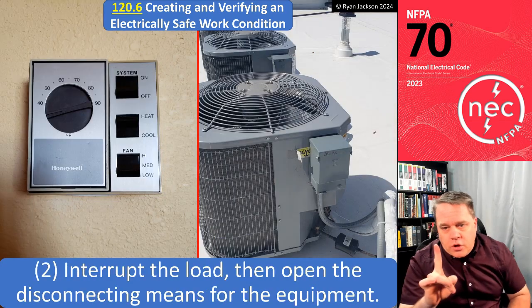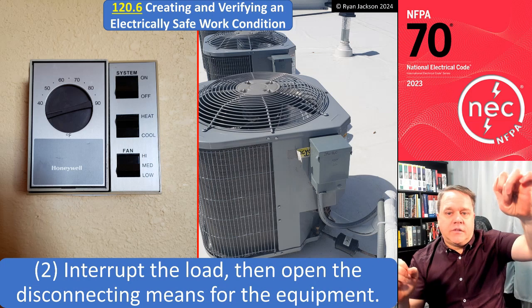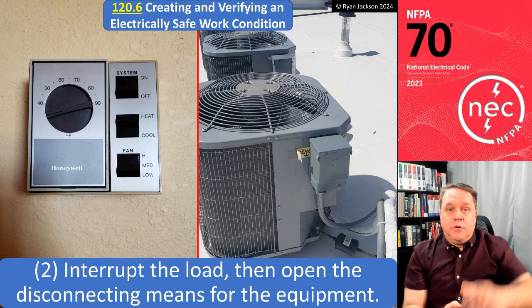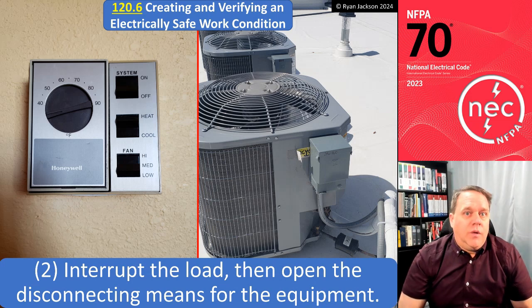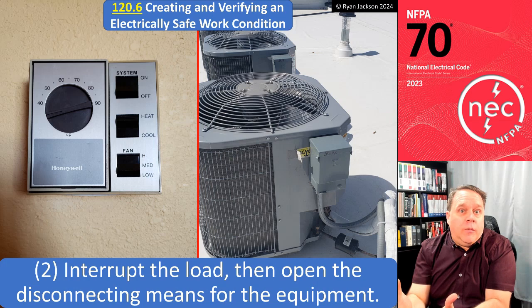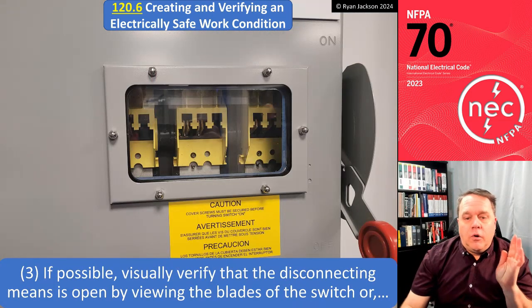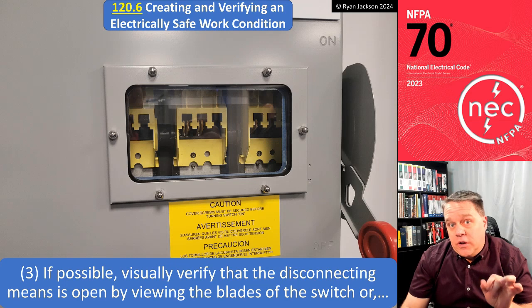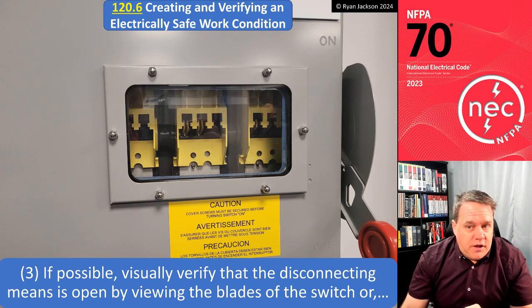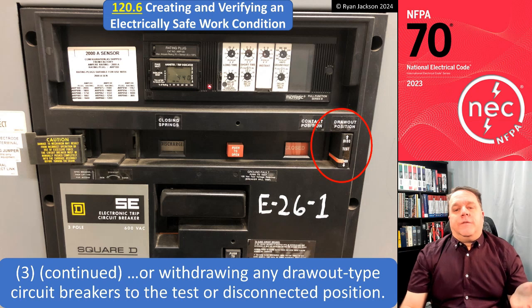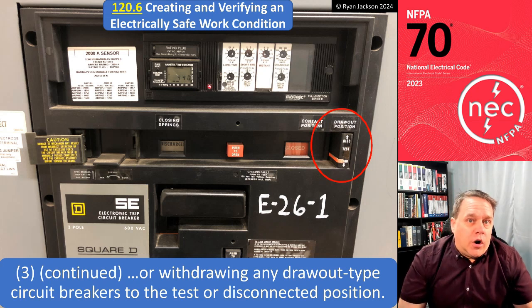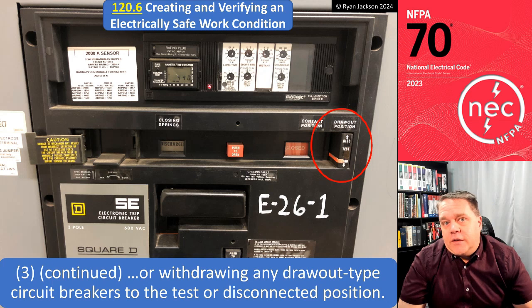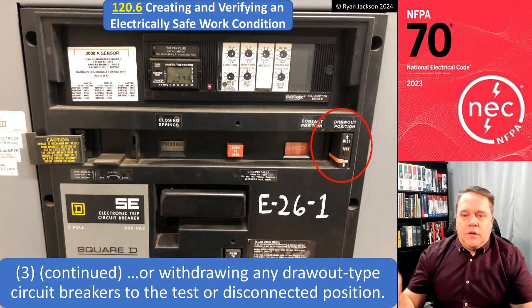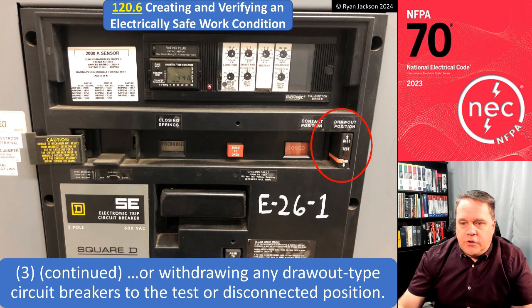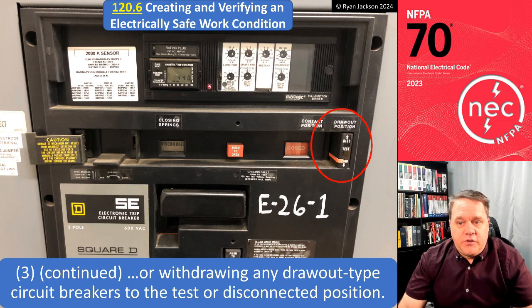Could I open the cover of that disconnect and watch the blades move? Sure, I guess, but we don't want you doing that. God, don't put yourself in harm's way in the name of safety, right? So yeah, if it's not going to increase your risk, go ahead and watch the blades move. Or if you're using a circuit breaker like this, withdraw any draw out type circuit breaker to the test or disconnected position. So you push the button, right, and you can see the draw out position. It says that it's open or it's under test position so that we know it's open.